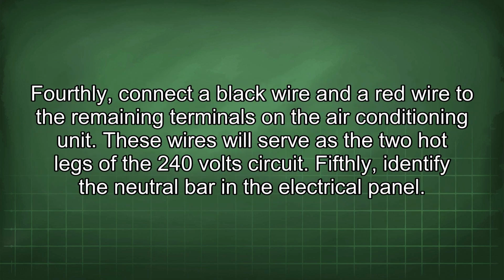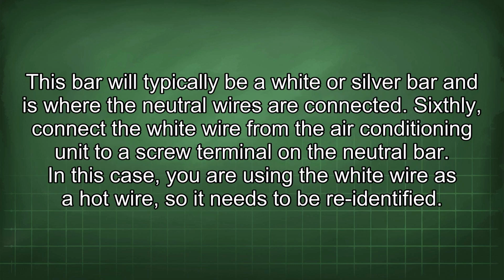Fourthly, connect a black wire and a red wire to the remaining terminals on the air conditioning unit. These wires will serve as the two hot legs of the 240-volt circuit. Fifthly, identify the neutral bar in the electrical panel. This bar will typically be a white or silver bar and is where the neutral wires are connected. Sixthly, connect the white wire from the air conditioning unit to a screw terminal on the neutral bar. In this case, you are using the white wire as a hot wire, so it needs to be re-identified.